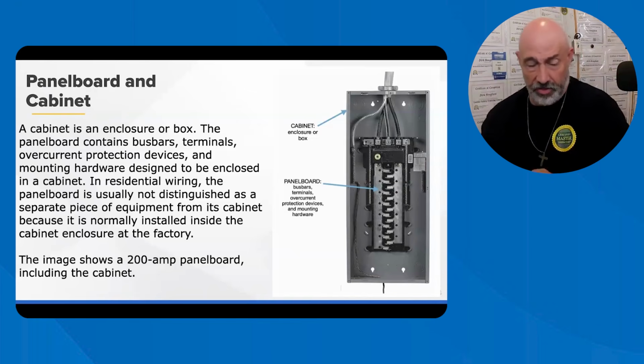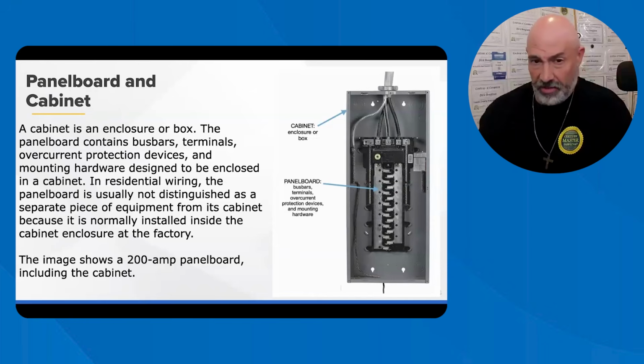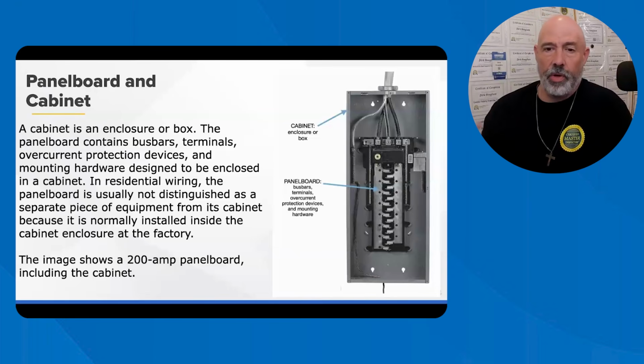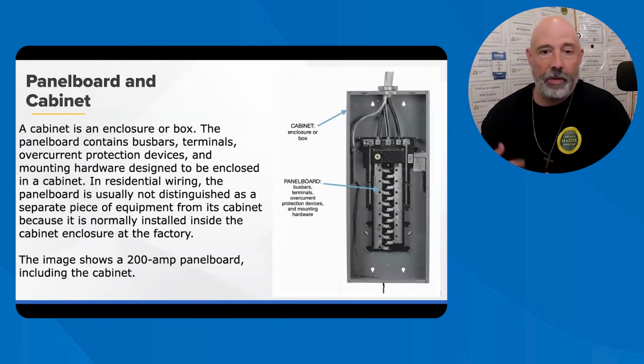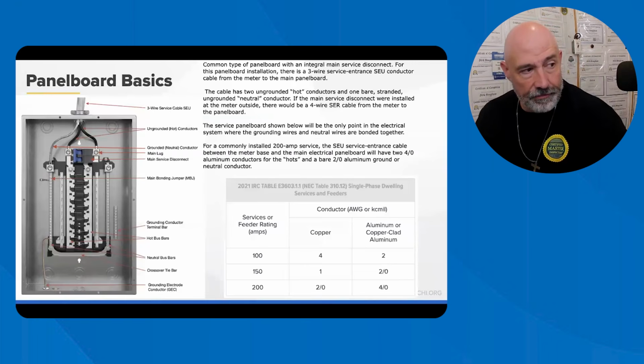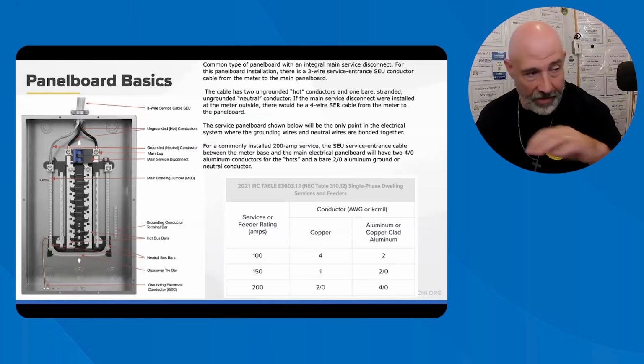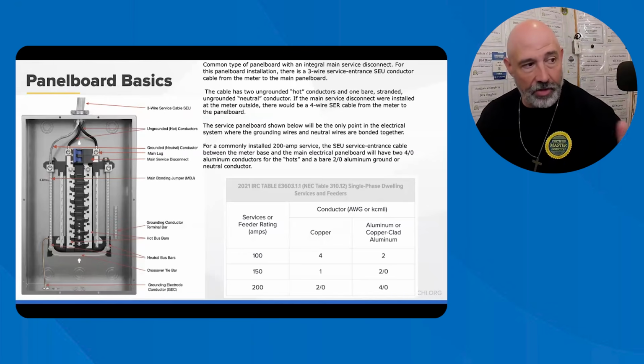If you see it overclogged, make sure that you're calling that out too, because too much is never good. Panel boards are usually installed near where the service enters into the house and is mounted to the structure itself. In basements, it's common to see panel boards mounted to the plywood to provide a solid backing so that they can actually mount it properly. We've talked about this before, and I'm not going to go through everything here, but here are your basic terminology of your panel boards, your bus bars, your main jumper wire. You want to make sure you're looking at all this stuff.